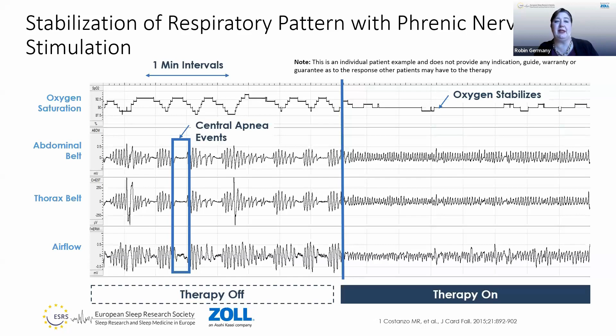So if you happen to have a high altitude patient, and they're hypoxic at baseline, they will still need oxygen. Sometimes people don't think about that because it's not delivering oxygen on its own, right? If they're hypoxic at baseline, they may still need a little bit of oxygen. Now, the device works a little bit differently than you might think, and some of that is lessons that we've learned over the years. The device actually has 2 algorithms in it. One is that it can augment a breath, so basically wait for the patient to take a breath and augment it.